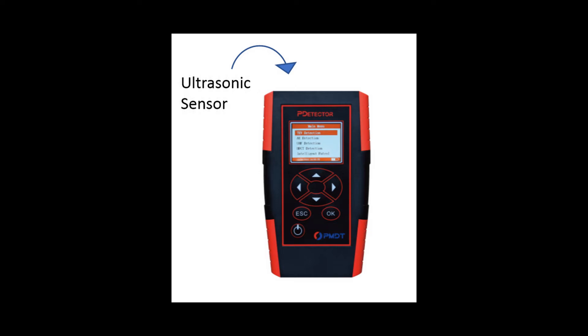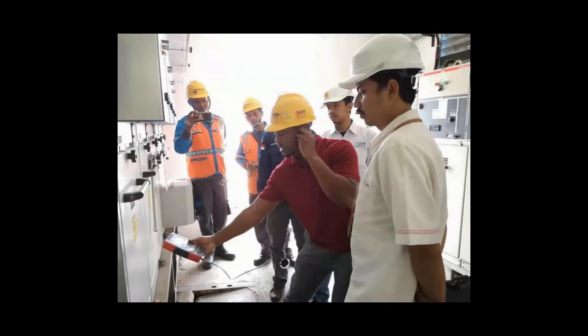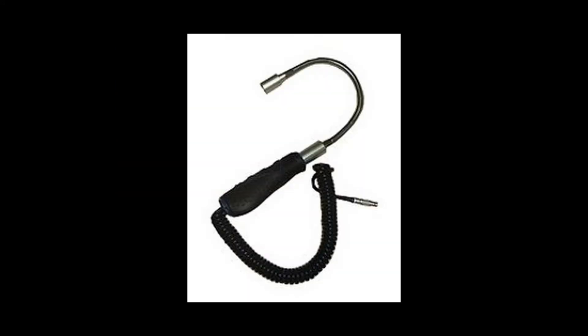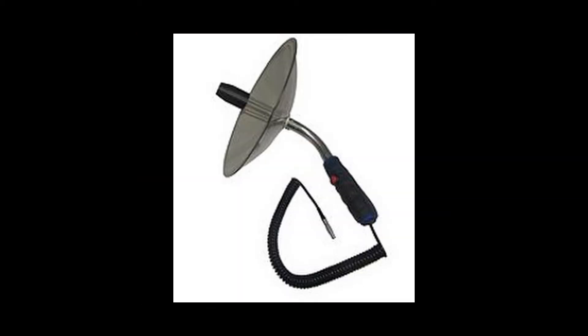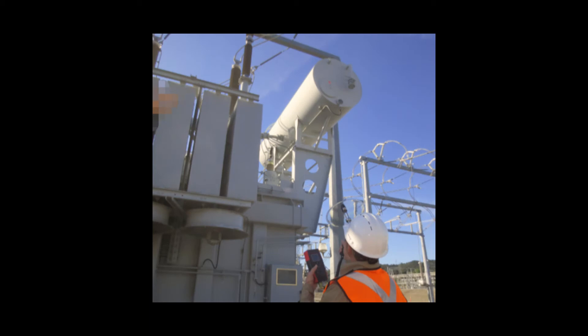The P-Detector employs three ultrasonic sensors: an internal sensor built into the main unit, an extension wand, and a parabolic dish. These three sensors are used to detect the vibration phenomenon of the ultrasonic signal spreading through air. It is mainly used for PD detection for electrical equipment which has passages with the air, such as switchgear and outdoor electrical equipment. It can convert the ultrasonic signals into audible sound through heterodyne techniques, and is best used to determine the existence of the PD as well as the location through listening to the signal's characteristic sounds.